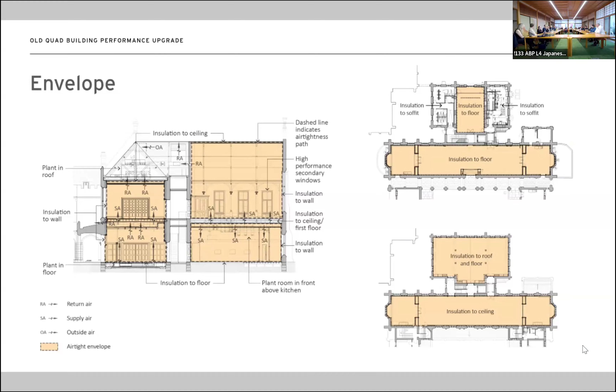And in Melbourne climate, for a large portion of the year, we have a lot of free cooling that comes in there. When we don't have free cooling available, what we used was pre-cooling of the outside air using indirect evaporative coolers. So if you're used to a swampy unit in your house, that will be a direct evaporative cooler, and that's putting moisture in the air and that's blowing into your house. We don't want that in a building such as this, because we create extra humidity and more discomfort. So what we did is you inject all that moist air in the exhaust air stream, and it goes through a heat exchanger, and that cooled heat exchanger pre-cools the incoming air. So that was our first stage, and then we used heat exchangers.